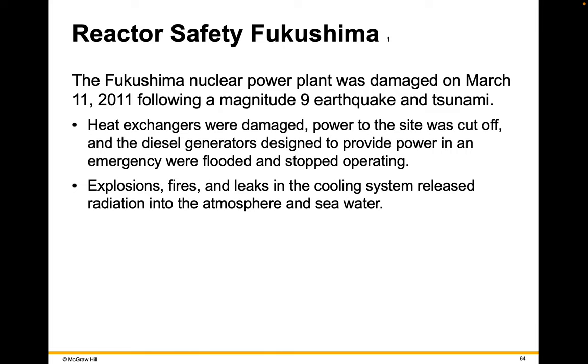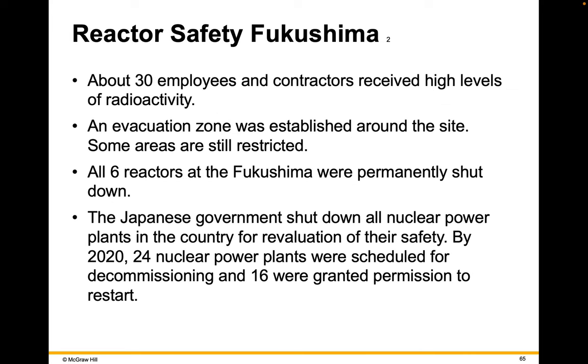The Fukushima nuclear power plant was damaged on March 11th, 2011, following a magnitude 9 earthquake and tsunami. Heat exchangers were damaged and power to the site was cut off. The diesel generators designed to provide emergency power were flooded and stopped operating. Explosions, fires, and leaks in the cooling system released radiation into the atmosphere and seawater. About 30 employees and contractors received high levels of radioactivity, and an evacuation zone was established around the site — some areas are still restricted today. All six reactors at Fukushima were permanently shut down, and the Japanese government shut down all nuclear power plants for re-evaluation of their safety. By 2020, 24 plants were scheduled for decommissioning and 16 were granted permission to restart.